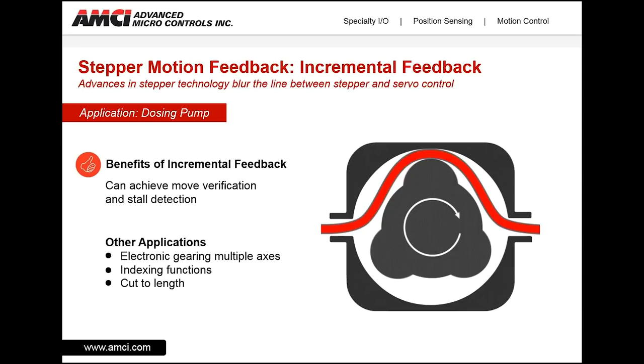One application that can take advantage of incremental encoder technology is a dosing pump. Dosing pumps are used to dispense precise amounts of liquid for filling applications and are used extensively in pharmaceuticals where repeatability and reliability are a must. The encoder feedback is used to verify the move was completed as expected. If something unexpected occurs during the move cycle, the control unit can use data from the incremental encoder to report that the move did not complete as expected and the system can react accordingly. Other applications that can benefit from incremental encoder feedback include electronic gearing, multiple axis indexing functions, and cut-to-length applications.